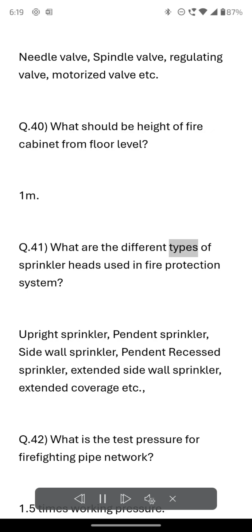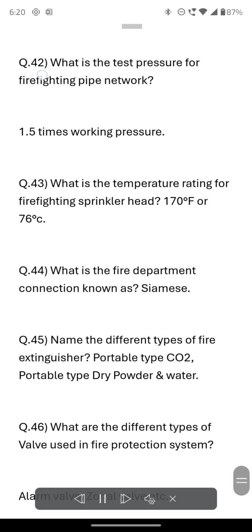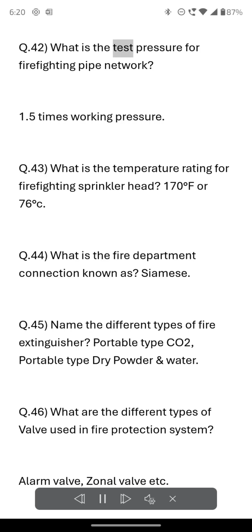Q.41 What are the different types of sprinkler heads used in fire protection system? Upright sprinkler, pendant sprinkler, side wall sprinkler, pendant recessed sprinkler, extended side wall sprinkler, extended coverage, etc. Q.42 What is the test pressure for firefighting pipe network? 1.5 times working pressure. Q.43 What is the temperature rating for firefighting sprinkler head? 170 degrees Fahrenheit or 76 degrees Celsius. Q.44 What is the fire department connection known as? Siamese.